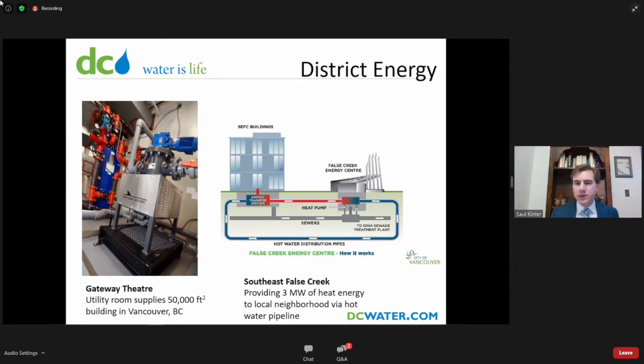But we're actually even more excited about the ability to scale this up and build large systems where we're distributing hot and cold water, or neutral temperature water, and providing the energy to make it at a pump station. The advantage here is that one of the big costs of doing wastewater thermal energy is accessing the sewer. For our headquarters building, it was easy because it was built on top of a pump station. For any other given building, you have to dig down to the sewer, and that can be quite expensive. So the potential we see is to build a central system where we have an energy center, possibly co-located with a pre-existing sewage pump station, so the sewage access is straightforward. And we distribute hot and cold water through pipes to the individual buildings.